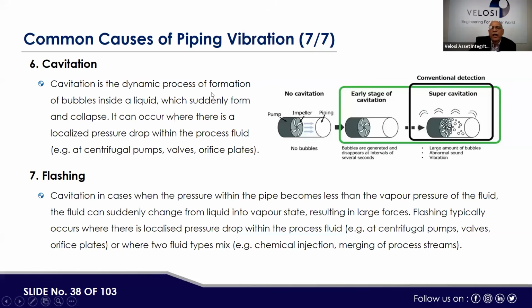Here, if you see, there is a pump impeller and piping. No bubble, no issue. In the early stage of cavitation, when any bubble comes, that bubble in the impeller will burst and it will cause supercavitation, right? So this is a normal phenomenon in the pump where we are designing pumps. The proper NPSH is ensured, and proper flow of the proper quality of fluid is also ensured, so that no air or gas mixes with the liquid and causes this cavitation.